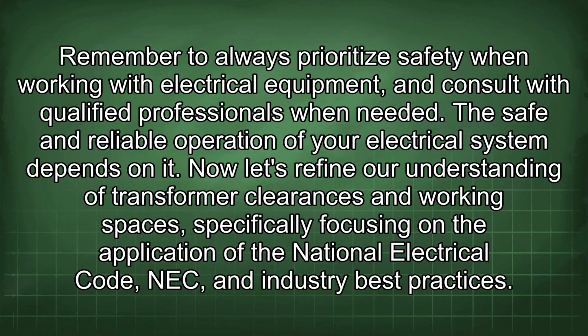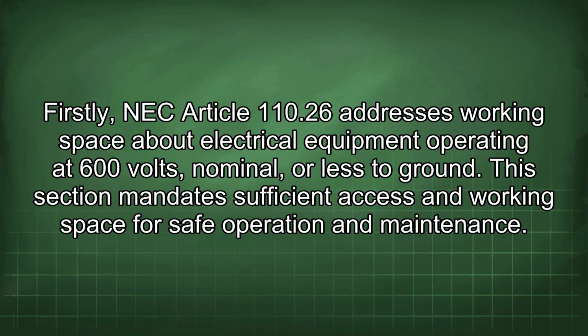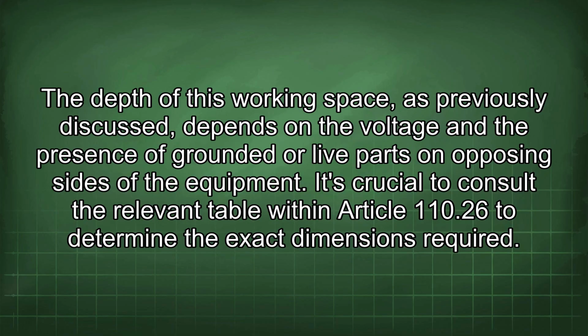Now let's refine our understanding of transformer clearances and working spaces, specifically focusing on the application of the National Electrical Code, NEC, and industry best practices. Firstly, NEC Article 110.26 addresses working space about electrical equipment operating at 600 volts, nominal, or less to ground. This section mandates sufficient access and working space for safe operation and maintenance. The depth of this working space, as previously discussed, depends on the voltage and the presence of grounded or live parts on opposing sides of the equipment. It's crucial to consult the relevant table within Article 110.26 to determine the exact dimensions required.